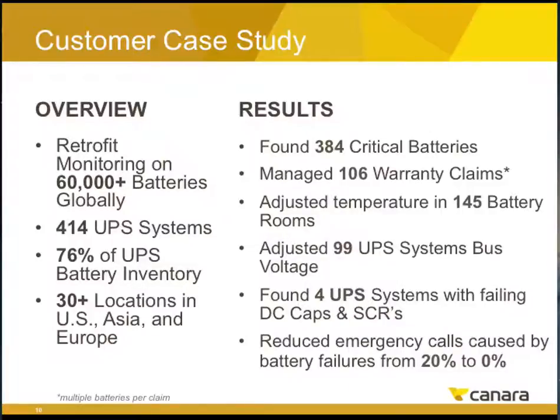In this particular instance, we found over 4 UPS systems that had failing DC capacitors and SCR boards. These are the kind of failures that can literally cause a physical explosion in the case of DC capacitors, and typically we'll bring that system down and make it unavailable in the event that utility power fails. As I mentioned, we're all about predictive analytics. Instead of handling emergencies as they occur, we want to monitor the systems and take the actions required to prevent emergencies in the first place. For this customer, 20% of their emergency service calls were bad batteries, and we moved that from 20% to 0%.